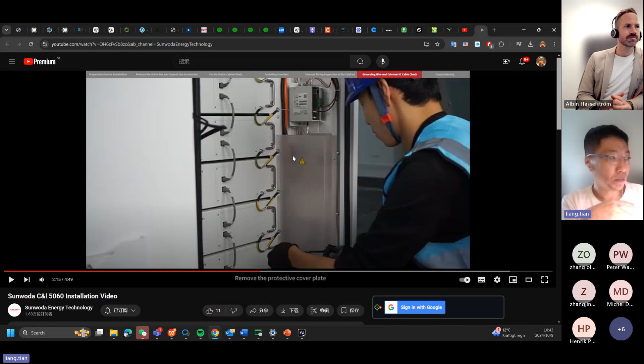The battery and inverter output are already pre-connected to the bus bar. If you want to combine multiple cabinets, the cable from the slave cabinet should be hooked up here to combine them on the DC side. Then here there's another rail - this is for the auxiliary power.